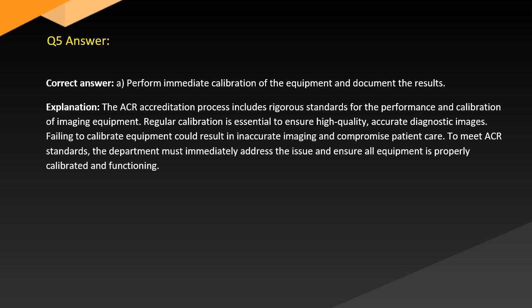Answer. Correct answer: A. Perform immediate calibration of the equipment and document the results. Explanation. The ACR accreditation process includes rigorous standards for the performance and calibration of imaging equipment. Regular calibration is essential to ensure high-quality, accurate diagnostic images. Failing to calibrate equipment could result in inaccurate imaging and compromise patient care. To meet ACR standards, the department must immediately address the issue and ensure all equipment is properly calibrated and functioning.